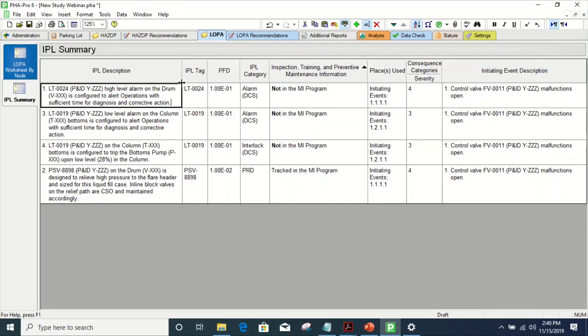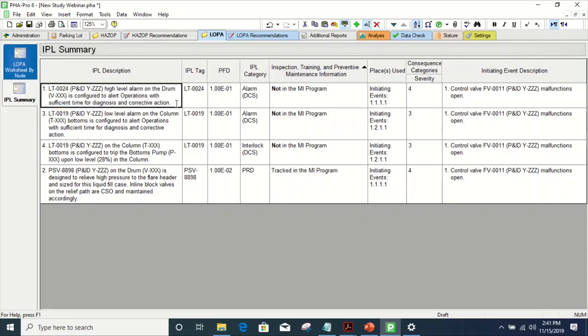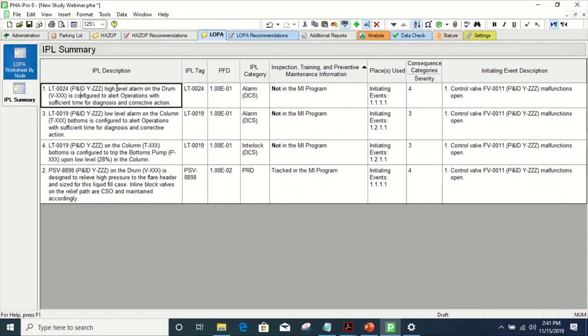What I have here in the worksheets is a list of safeguards in the LOPA tab. These are IPLs — Independent Protection Layers — basically safeguards that you take credit for in the LOPA. You have more rigorous considerations to take credit for a safeguard in a layer of protection analysis, but nonetheless they are safeguards. We'll go through the columns and information displayed in this safeguard summary list. For example, in the description I have the tag number and the P&ID number that it's located on. This is very helpful when you're searching through all the information — especially in studies where you might have hundreds of safeguards — so it's important to keep organized with the P&ID numbers and tag numbers.